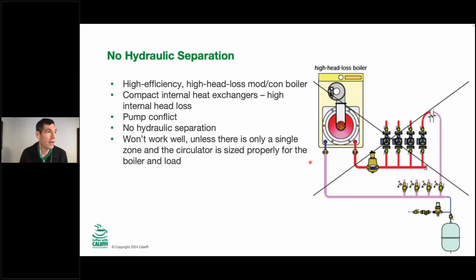So that's why this hydraulic separation came up, that like, hey, wait a second, we now have a piece of equipment that really wants a specific flow rate, and we kind of need to change our piping to adapt to that. There are plenty of these systems out there where the ModCon came out. Maybe you're lucky enough to have a couple unions in between, and maybe this is just soldered straight through to kind of do the easiest copy and paste with a new boiler technology, but you're not really setting up any of the equipment for success there. We'll go through some examples why in the next few slides here.